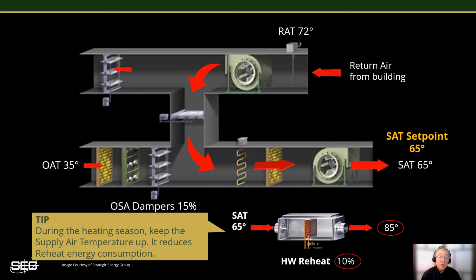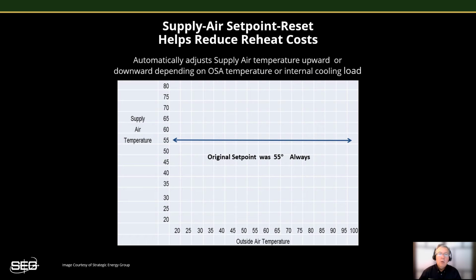So when heat is required in most of the zones, keep the supply air temperature up in its set point range and lower it only as the need for cooling becomes predominant, such as in late spring and summer. Early on, many of these systems were originally designed to use a constant supply air set point of 55 degrees, no matter what the heating and cooling loads were. But nowadays, with the much better control systems we have, these old, fixed supply air temperature set points are considered wasteful. That low of supply air is usually only needed during the warm weather of summer, and as a result, only drives up reheat costs during the other seasons.